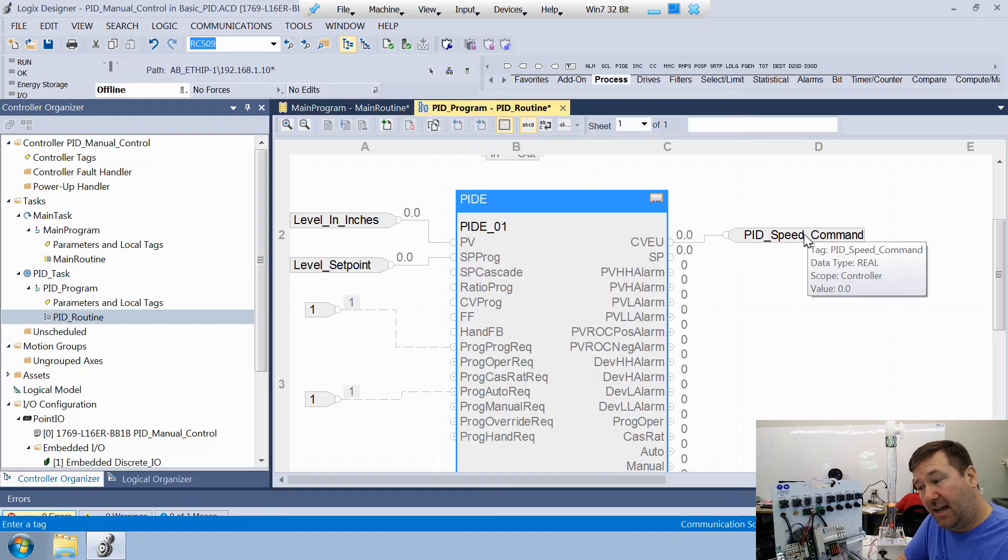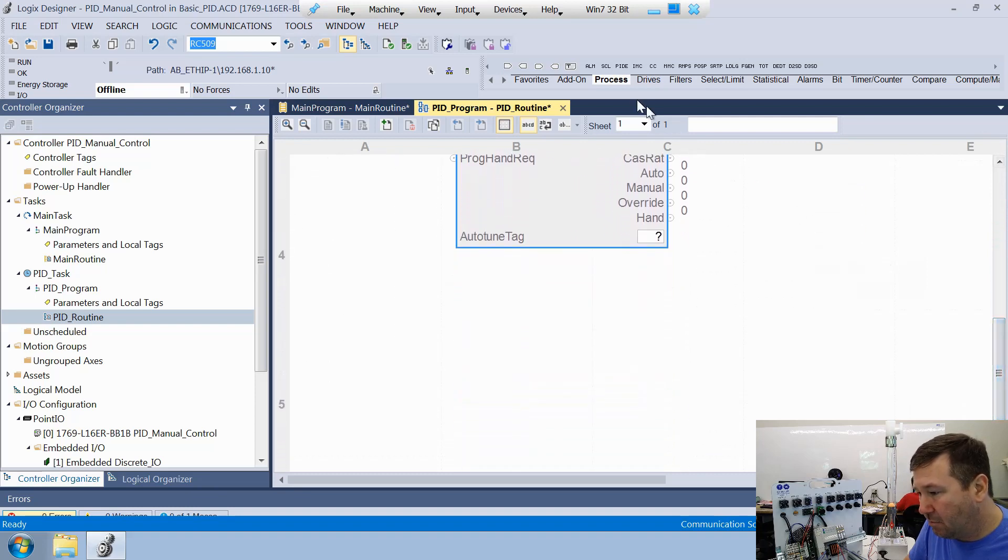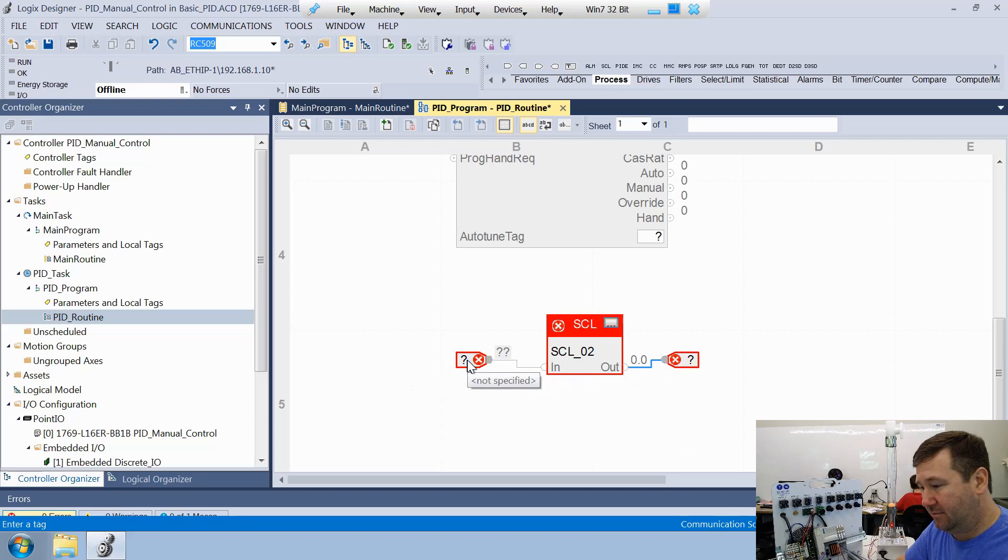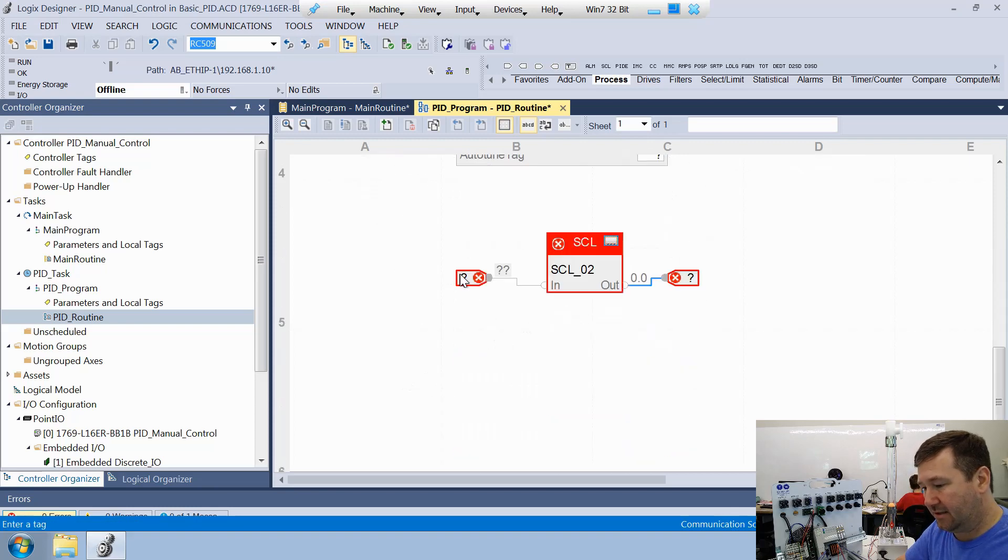And that should get our PID speed command putting out a value, but this is just a tag. So we do have one final step where we need to take that speed command and put it to that drive speed output. So we're going to add another scale instruction. We'll bring it down and we're going to grab an input reference and an output reference. And yes, somebody will put in the comments, yeah, I could have just put this drive output right on the PID, but we're going to do some other things later where it's going to become important that we have that little separation point. So we're going to click some connectors and then this will be that PID speed command. That's going to be our input.